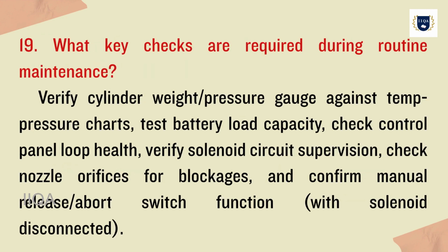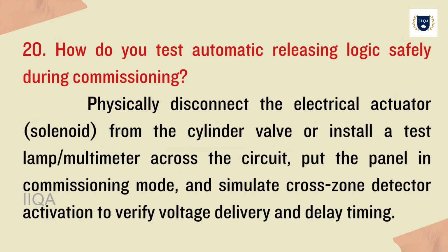19. What key checks are required during routine maintenance? Verify cylinder weight and pressure gauge against temperature-pressure charts, test battery load capacity, check control panel loop health, verify solenoid circuit supervision, check nozzle orifices for blockages, and confirm manual release and abort switch function with the solenoid disconnected.